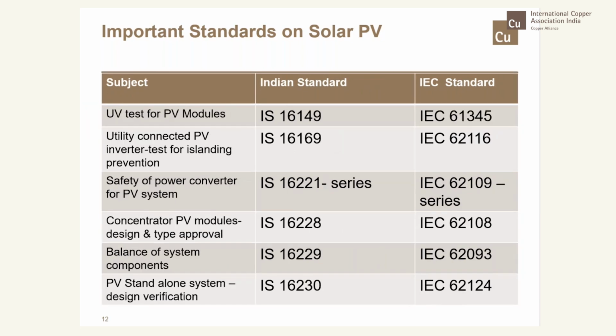The other standards, like UV test for PV modules, is IS 16149. Corresponding IEC standards are there. Utility connected PV inverter: there is a test for islanding prevention. That is a very important test. This is IS 16169. Safety of power converter for PV system is IS 16221 series.